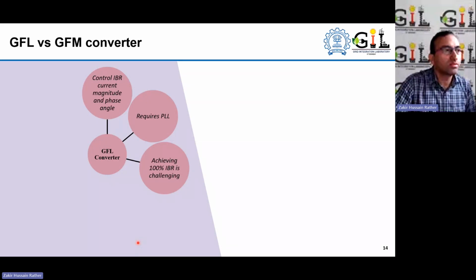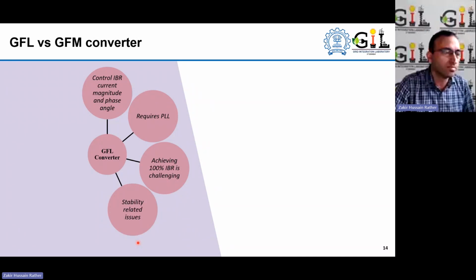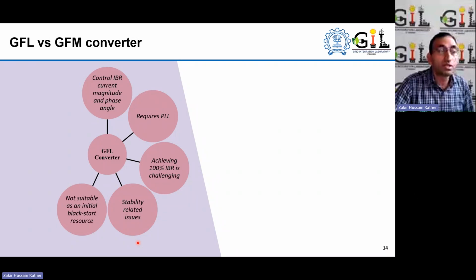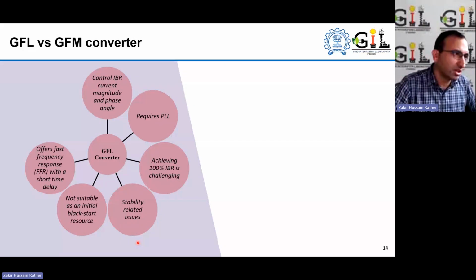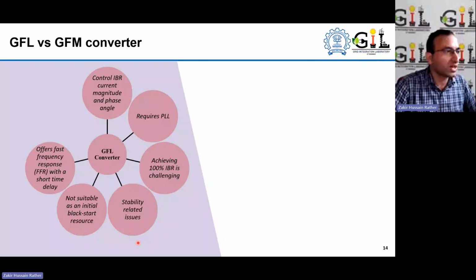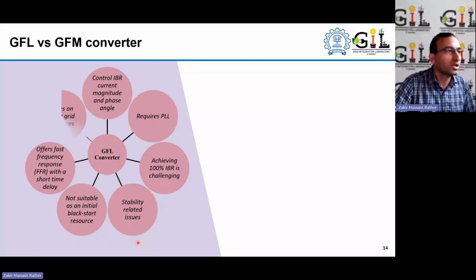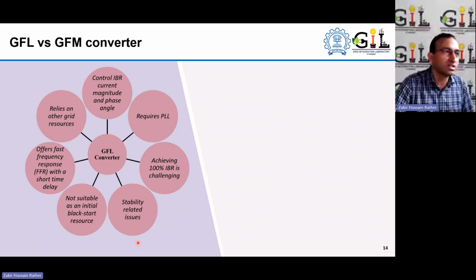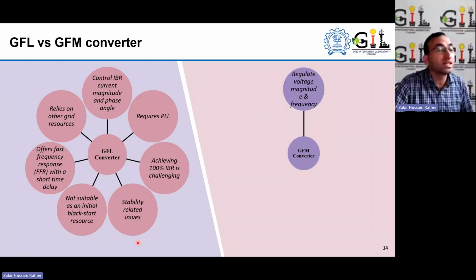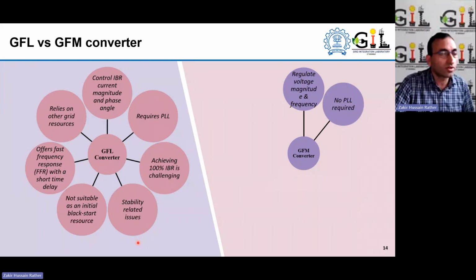Technically speaking, you cannot achieve very high penetration of IBRs with this grid following technology, because there are a lot of other challenges introduced in the system. There are stability related issues, as I briefly mentioned earlier. It's not suitable for the black start capability, to be precise, at the start. Later on, once the grid has partly recovered or started, then they can supplement that, but on their own they cannot participate in the black start capability of the system. It does have a faster response, but there is a delay associated with the measurement of the parameters and the control loop delays. As I mentioned, it needs the external grid. So in contrast, the grid forming technology can regulate voltage magnitude and frequency from the inverter side.